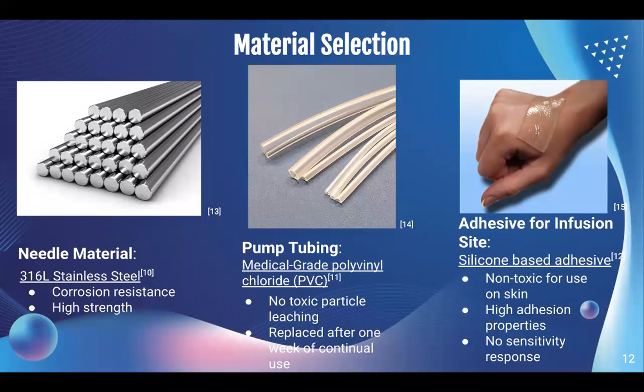For each of the major components that will be in direct contact with the patient, we have chosen the following materials. 316L stainless steel will be the needle material for both the pump and TSH sensor. It will stay in the body for up to 1 month and has high corrosion resistance and strength. The pump tubing will be medical grade PVC. This will be replaced after a week of continual use and no toxic particles will be released under this time period. Lastly, a silicone-based adhesive will secure the infusion site to the patient. This adhesive is non-toxic, has high adhesion properties, and in most cases does not elicit a sensitivity response.